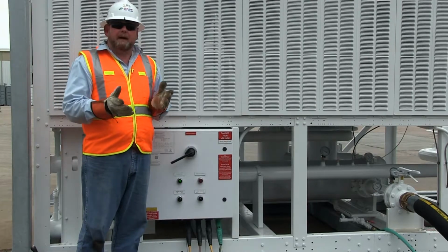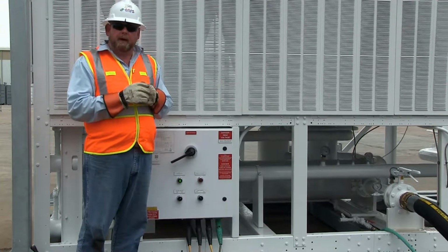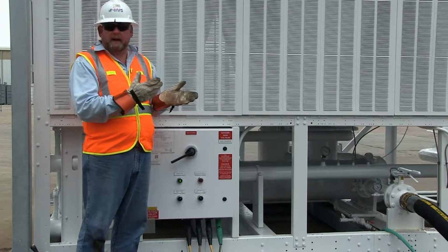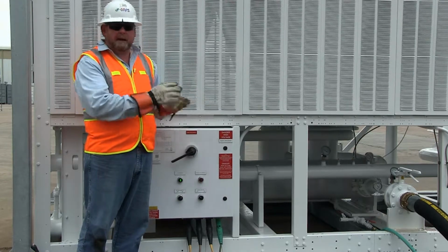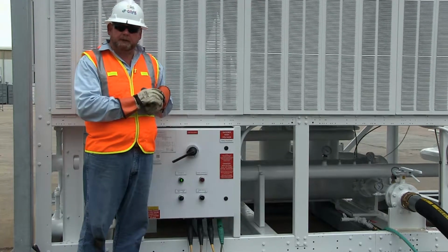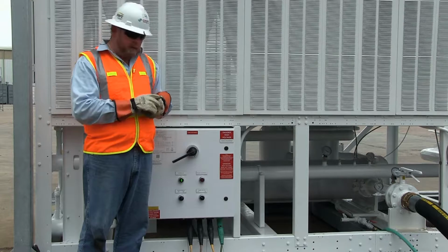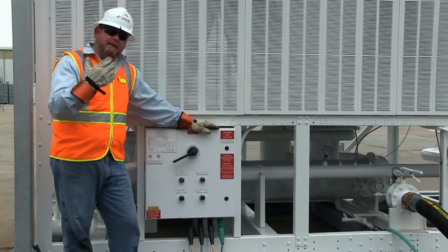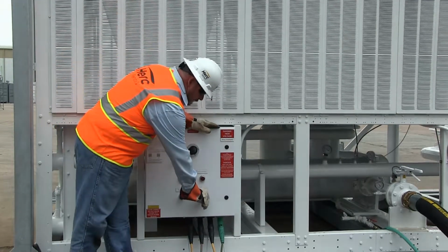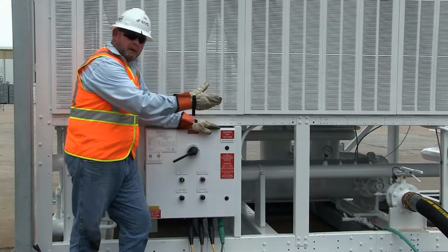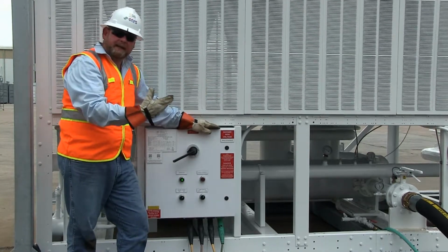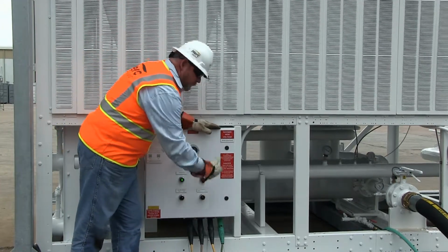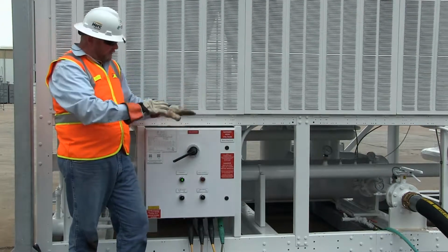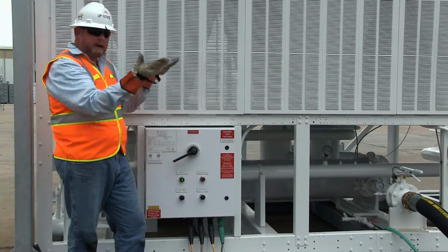Okay, it took us about 3 or 4 different cycles of the pump, but we've gotten all the air out of the system. We still have about a 50 psi standing pressure, which is perfectly fine. We did the process of bleeding the air out by simply turning the switch on. You can hear the pump come on. We leave it on for 4 or 5 seconds. Let it move the water around, move the air around. If I turn it off, all the water falls, all the air goes up.